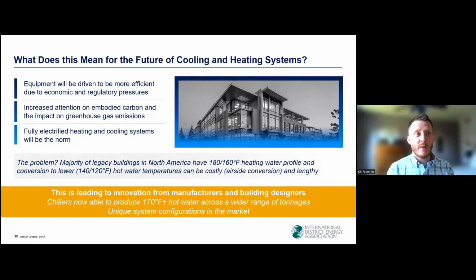And that will be mainly driven by heat pumps, both direct expansion and hydronic, which we'll cover at length today, along with technologies that enable us to store and reuse energy in buildings. On top of this, the equipment that you are normally accustomed to using today may change in how it's controlled. An example of this could be no longer applying airside economizers, so you can leverage heat sources for your heat pump systems. And we'll talk about that more a little bit later.